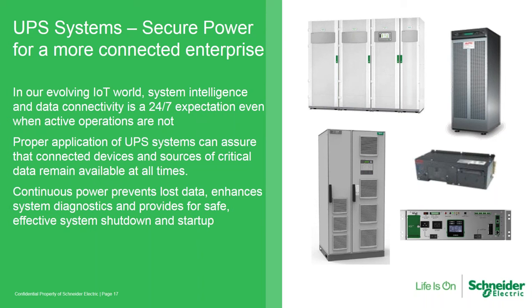Well, lost data, enhanced systems diagnostics, certainly. If you've been around these systems, one thing you know is quite often the system diagnostics during a power failure or partial power failure are just a cascade of meaningless faults that are actually a result of communications interruptions, power interruptions, and not necessarily pointing you to meaningful information, and in fact clouding your ability to see meaningful information from historical data. Also helps provide for safe and efficient system shutdown and startup.